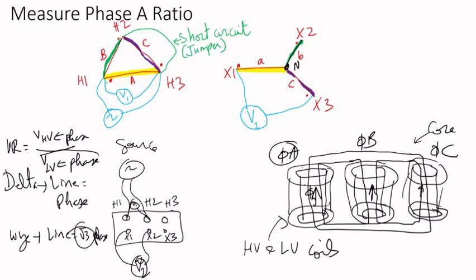So what you do, for instance, if I want to measure the voltage for phase A, I like the IEEE convention and other documents: uppercase A, lowercase a, to differentiate. Uppercase A is the high voltage, lowercase a is the low voltage. I could have called them AH and AL or something. To make it simple, uppercase A, lowercase a means phase A. Then I connect a voltmeter across phase A, between H1 and H3, and I connect a source between H1 and H3, which is phase A.